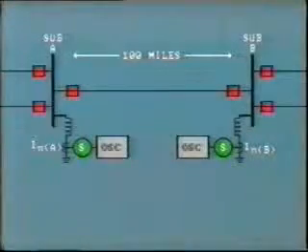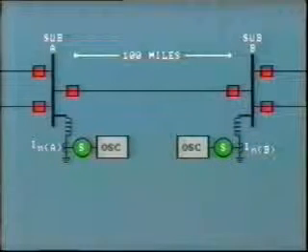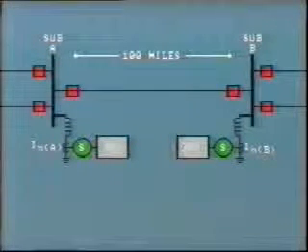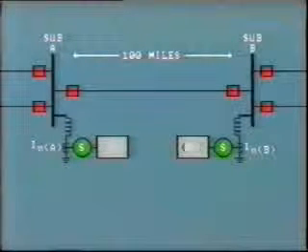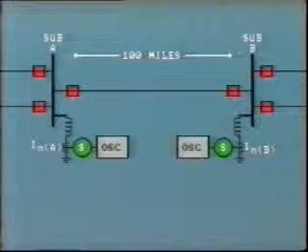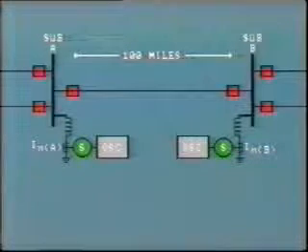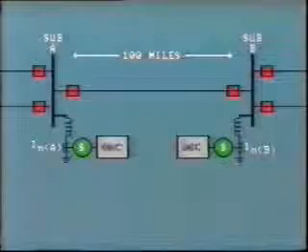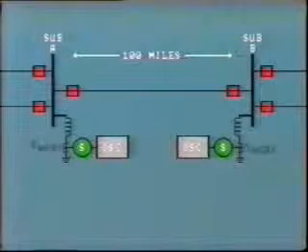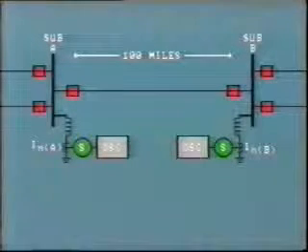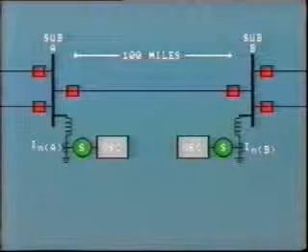Here's an example of how oscillograms, along with some computer simulations, can help pinpoint the location of trouble areas along a transmission line. The system one-line diagram shows two substations, A and B, separated by 100 miles of line. Both stations are equipped with oscillographs that monitor transformer neutral currents, INA and INB. This installation suffers a particular problem.